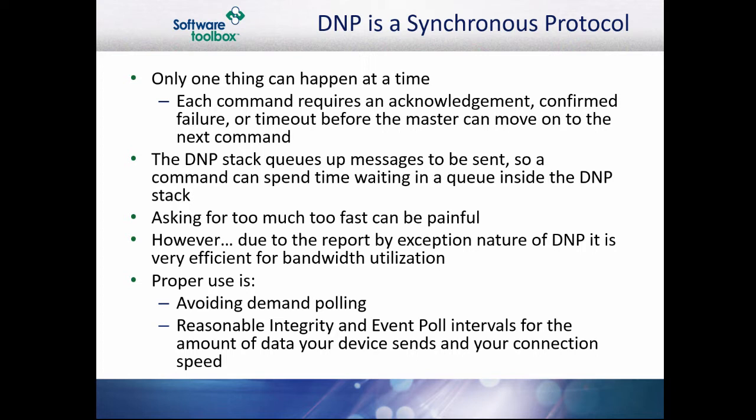Due to the report-by-exception and unsolicited messaging features, DNP3 is very efficient in bandwidth usage, which is important with wireless or cellular communications. To reap the benefits of the DNP3 protocol, avoid demand polling and use reasonable integrity and event poll intervals given your transmission method and amount of data needed.